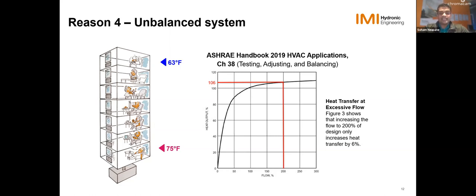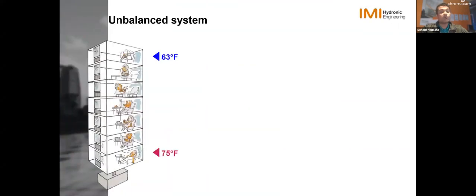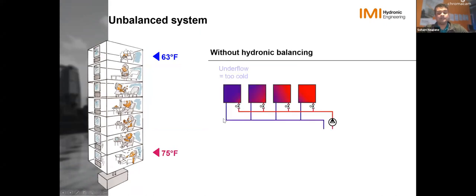So let's dive into more detail of balancing and different ways to balance them. So balancing the water flow rate, right? It's important, as we said. Water's lazy, it's going to take the path of least resistance. So when you have a system like this, where you don't have proper balancing and you just have control valves, what happens? You look at this circuit closest to the pump, that's the easiest to satisfy. So your water is lazy, most of the water is just going to go through this supply, come back through that return.